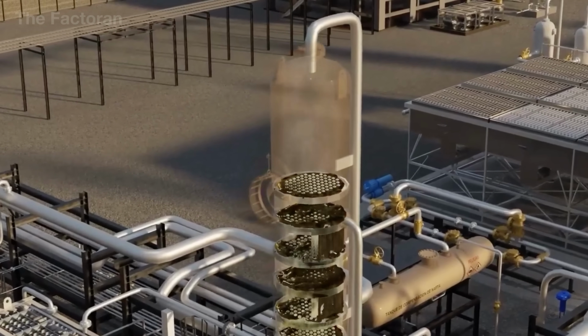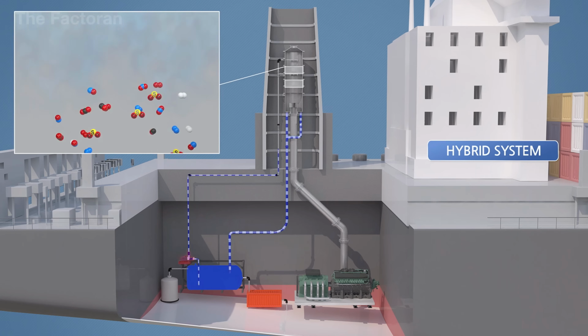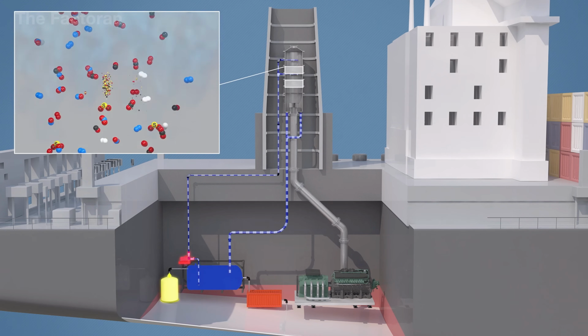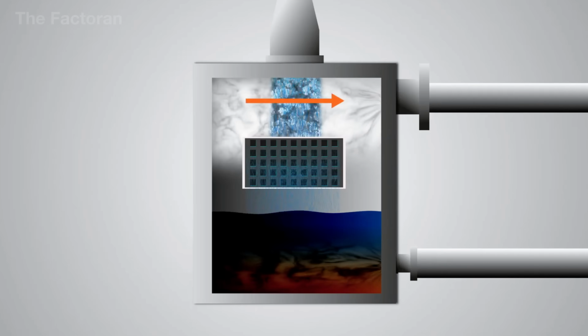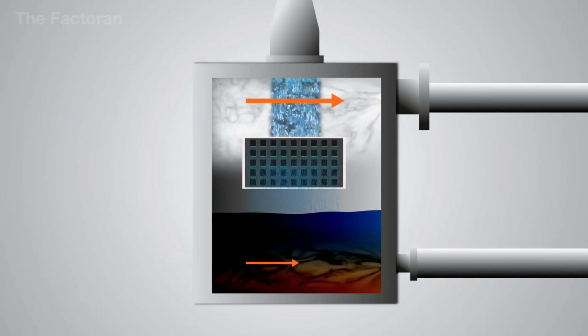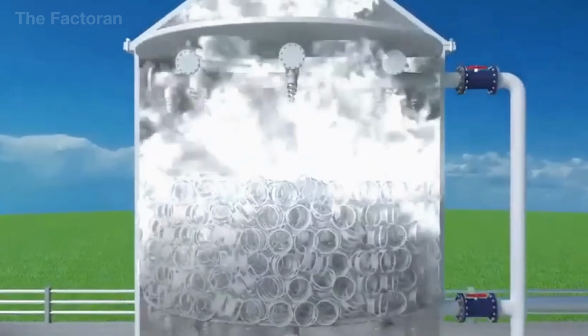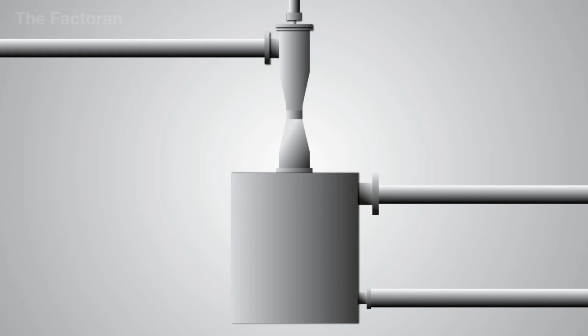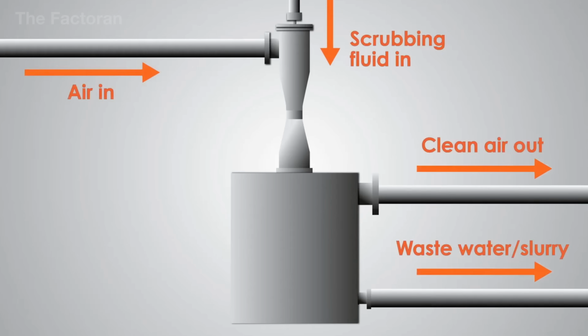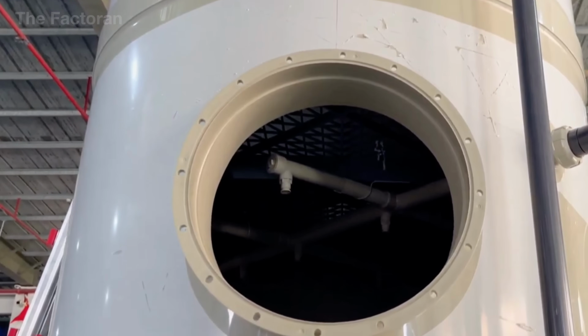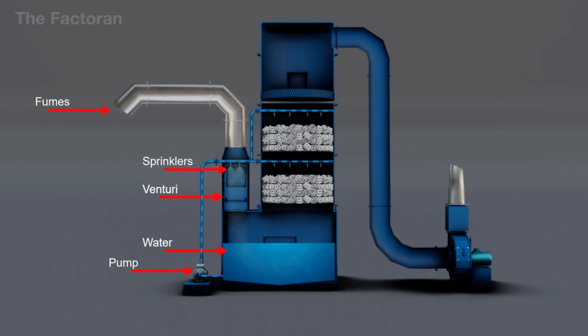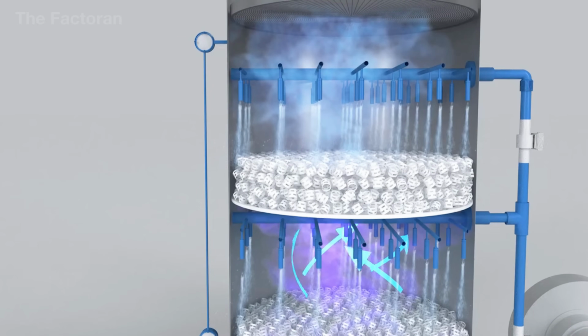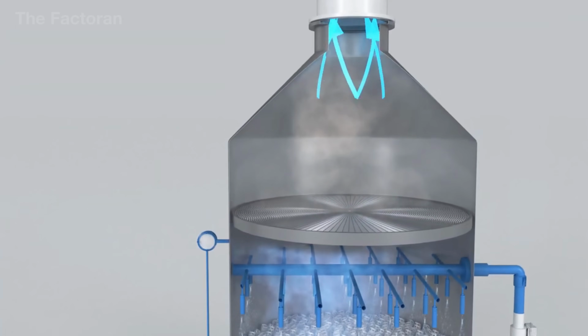During impact and dissolution, SO2 and other acid gases are converted into neutral salts and moist sludge, which gradually settles at the base of the tower. The sludge is collected in a recirculation tank, where water is separated and the remaining effective solution is reused. The purified gas then passes through a demister, which captures fine liquid droplets to prevent them from escaping into the atmosphere. The system operates fully automatically, with sensors controlling temperature, flow rate, and pH levels. Thanks to its multi-stage spray design and the rapid reactivity of alkaline solutions, the wet scrubber achieves an acid gas removal efficiency of over 95%, ensuring that the treated air meets emission standards before moving on to the final stage.